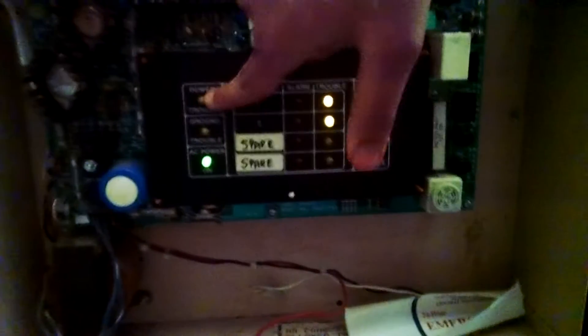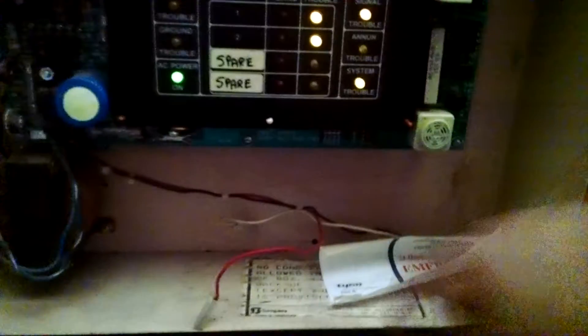That system trouble's just on because the rest are on. I should be getting a power trouble because I don't have batteries, but the building the system came out of might not have had batteries. I'll figure that out once I clear the rest of the troubles and see if it clears itself.